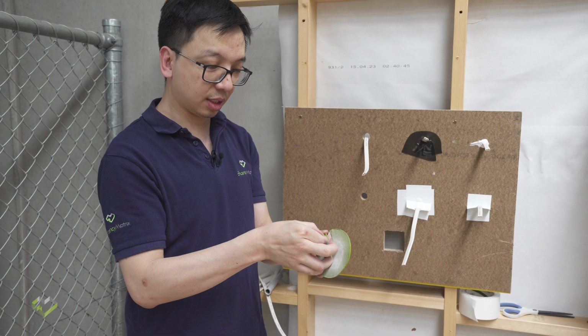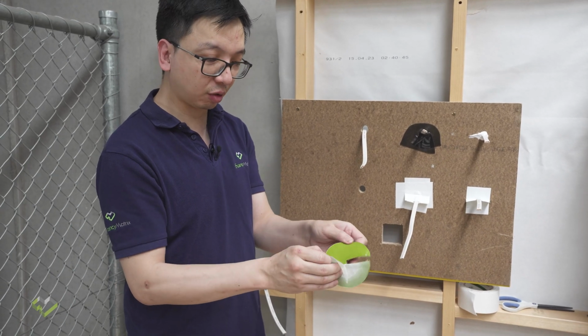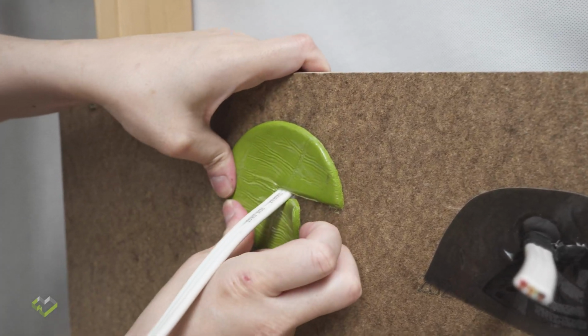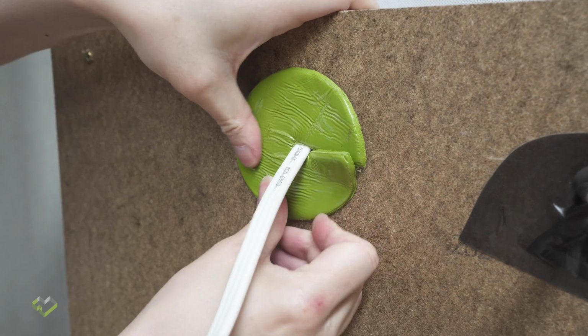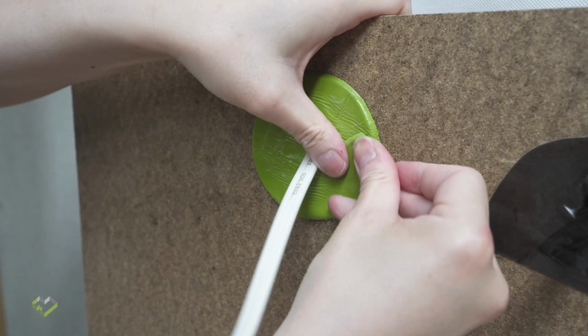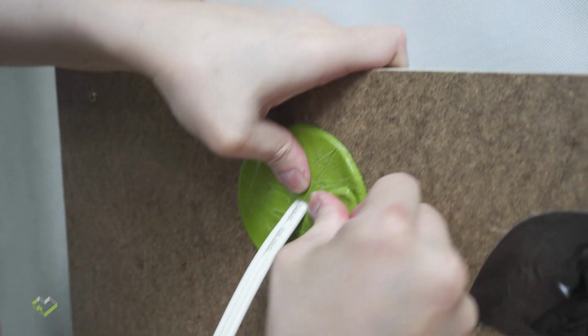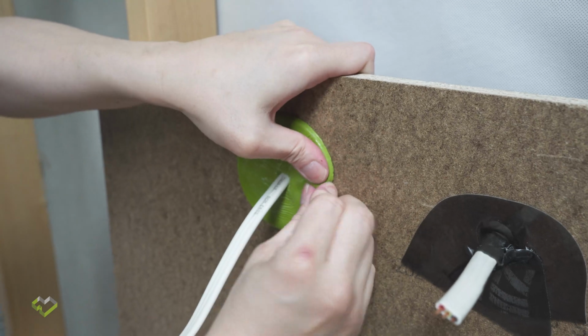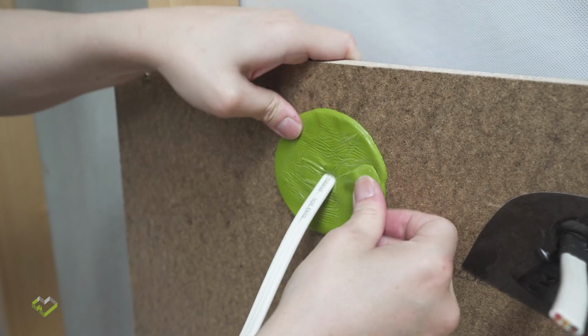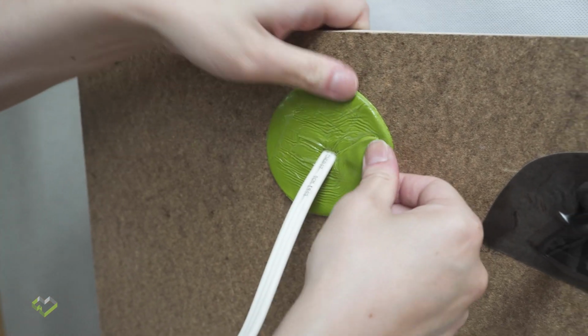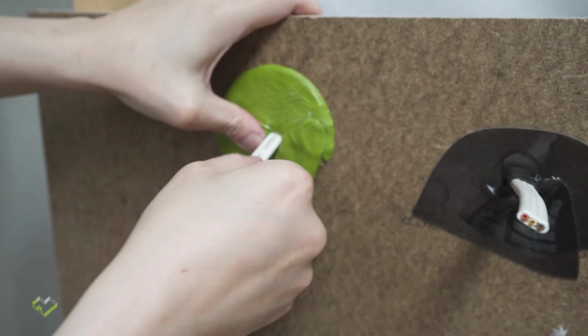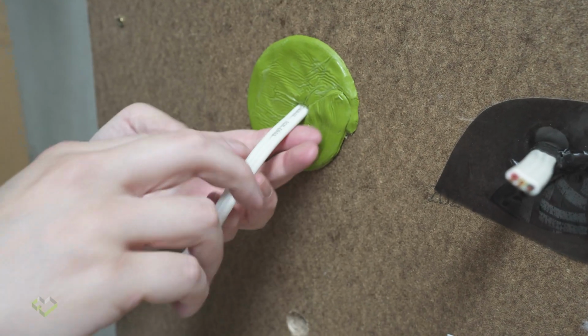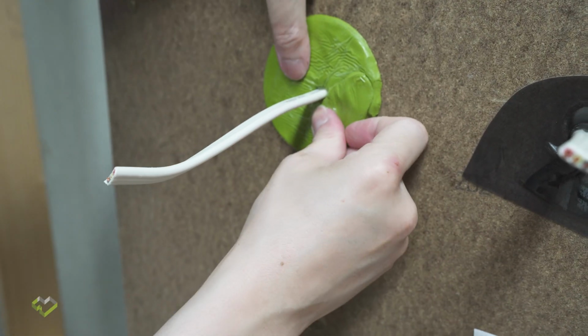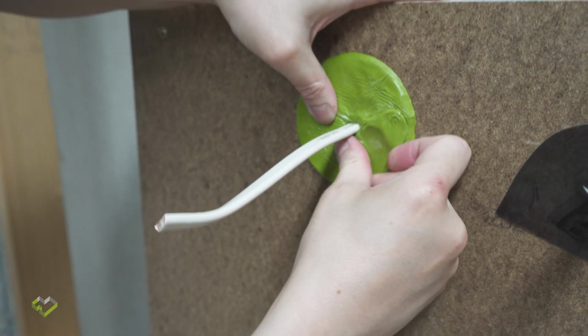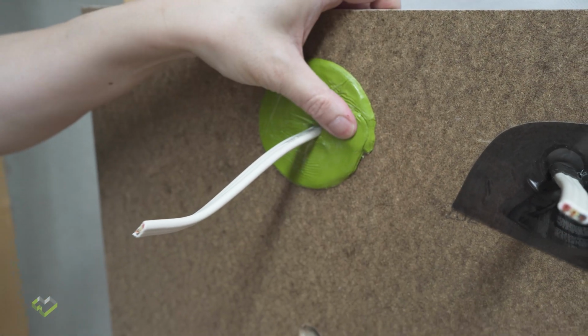All you need to do is remove the backing, the release liner, from the side, slice it to the cable, and then you push it, work it, it will adhere to the substrate, and then you can mold around your cable. You can also use this on conduits and smaller pipes. This is moldable and is not fully stuck to the pipe or the cable.